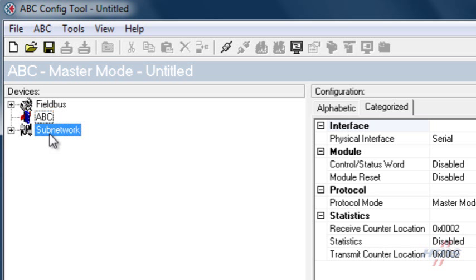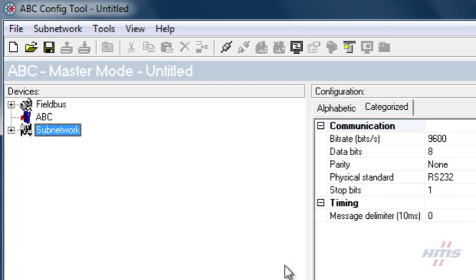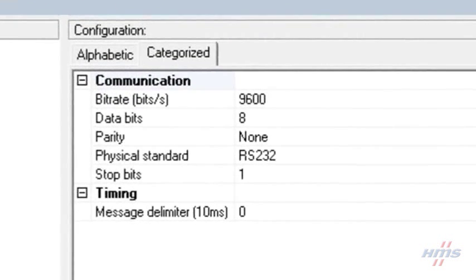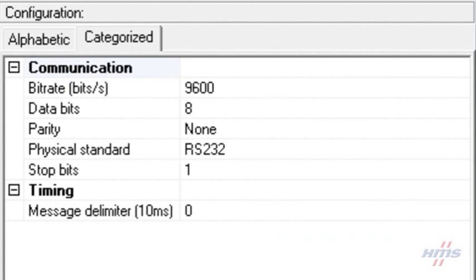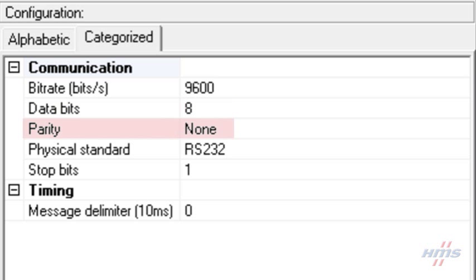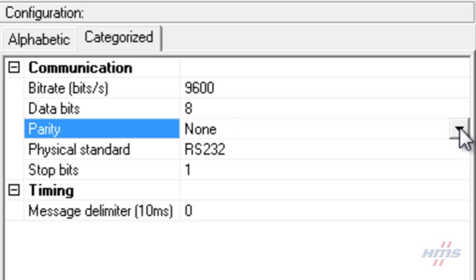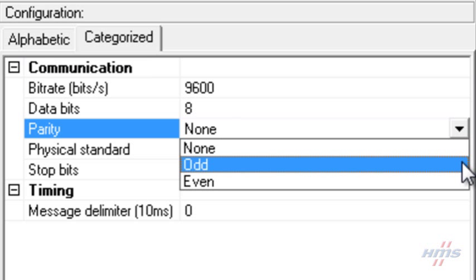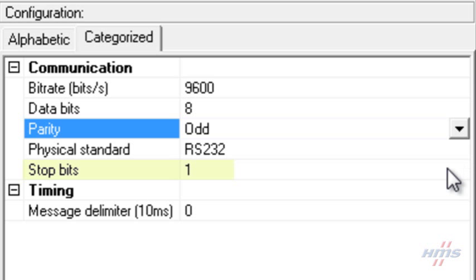The ABC communication properties have already been configured and we need to configure the communicator with the same settings, which are 9600 bits per second, 8 data bits, 1 odd parity bit and 1 stop bit.